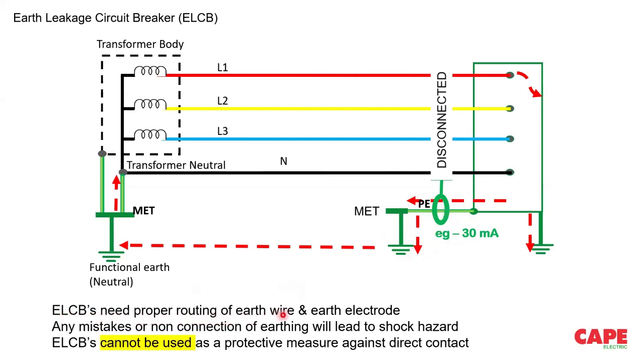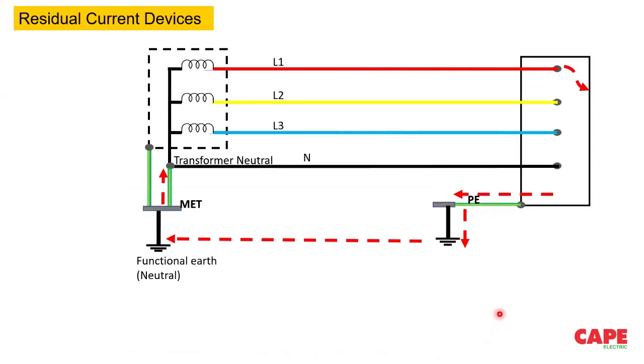ELCBs need proper routing of earth wire and earth electrode. Any mistake or non-connection of earthing will lead to shock hazard. ELCBs cannot be used as a protective measure against direct contact. Nowadays, ELCBs are not much available in the market, especially in India. I don't know about other countries.